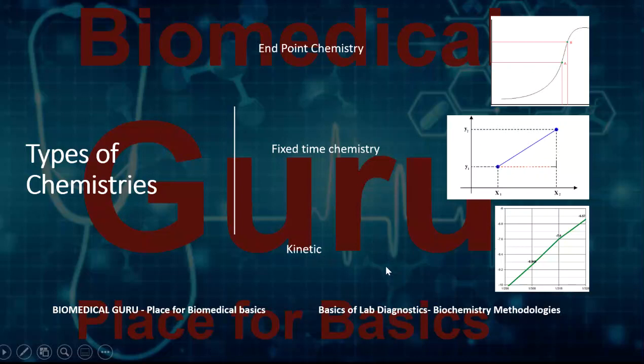And then comes the kinetic chemistry. In kinetic chemistry, the rate of change of absorption over a period of time is analyzed. In this case, if you see after 5 minutes, whether you have less concentration of the analyte or more concentration of the analyte, the end result will be the same. So here we measure how fast the analyte is able to change the absorption, that is kinetic. Kinetic is generally used to measure SGOT, SGPT kind of chemistries.